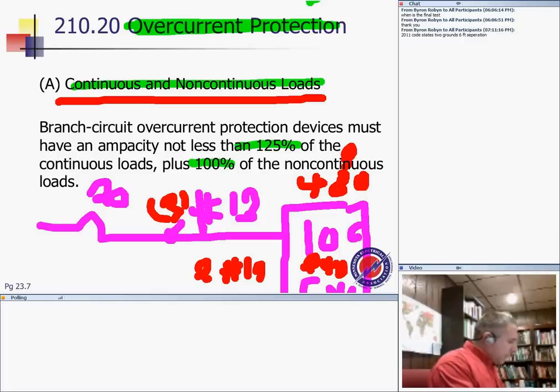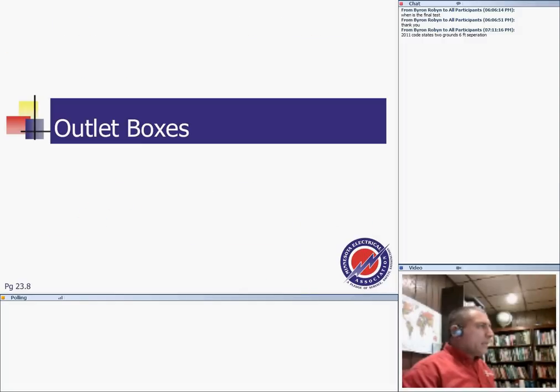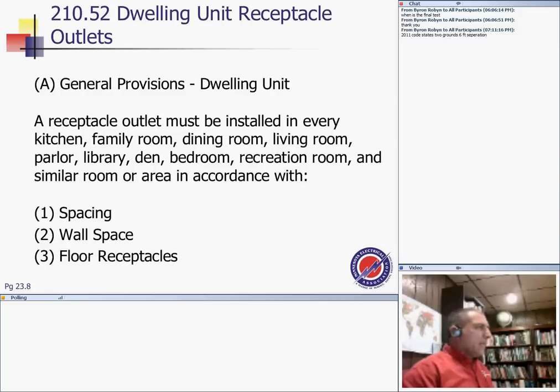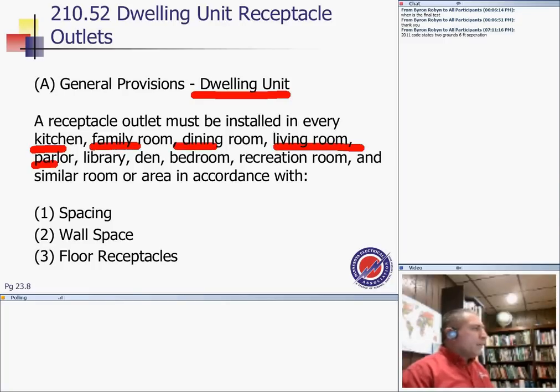We talked about grounding, and the last part, guys, is laying out outlets and lights, laying out outlet boxes, receptacles and lights in residential. If you guys are not familiar with Article 210.52, get familiar with it, because it will give you a lot of things. Receptacle outlets, general, in dwellings. Remember, we're not in hospitals, we're in dwellings. A receptacle outlet must be installed in every kitchen, family room, dining room, living room, and habitable rooms like den, bedroom, recreational rooms, and similar areas.